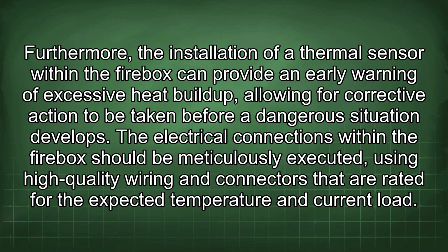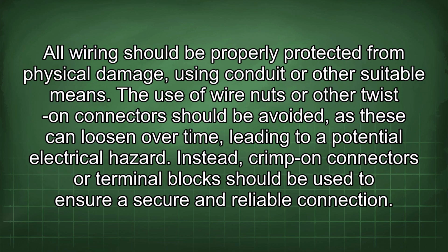The electrical connections within the firebox should be meticulously executed, using high-quality wiring and connectors that are rated for the expected temperature and current load. All wiring should be properly protected from physical damage, using conduit or other suitable means. The use of wire nuts or other twist-on connectors should be avoided, as these can loosen over time, leading to a potential electrical hazard. Instead, crimp-on connectors or terminal blocks should be used to ensure a secure and reliable connection.